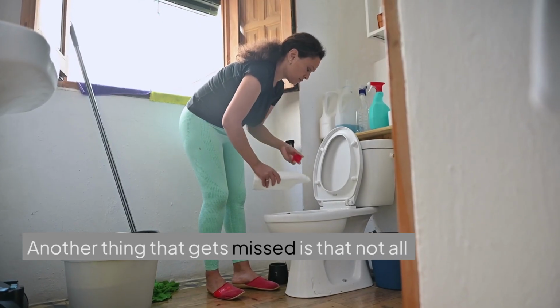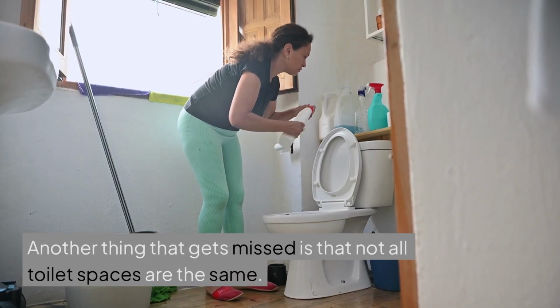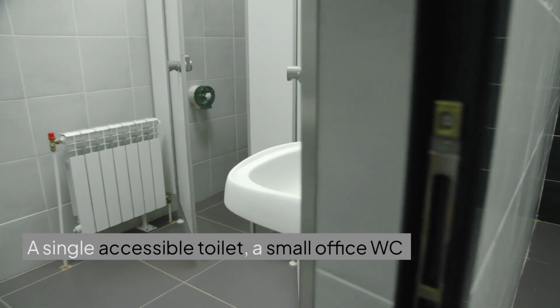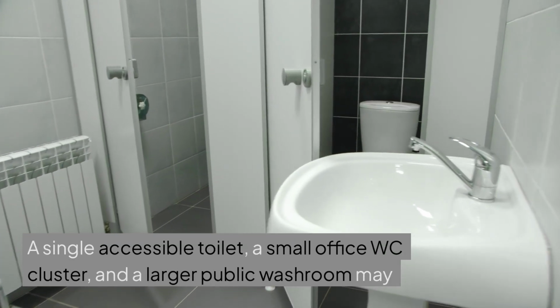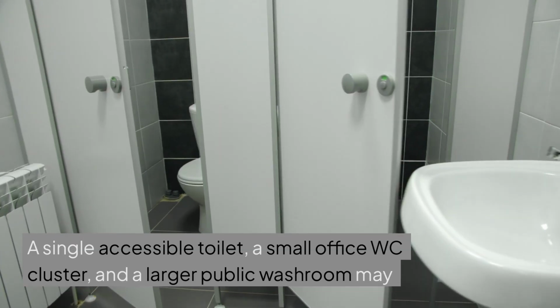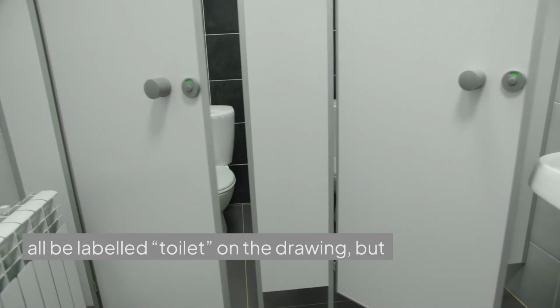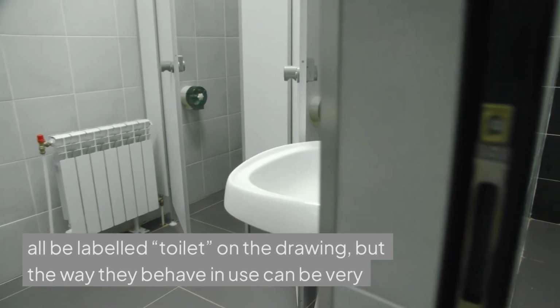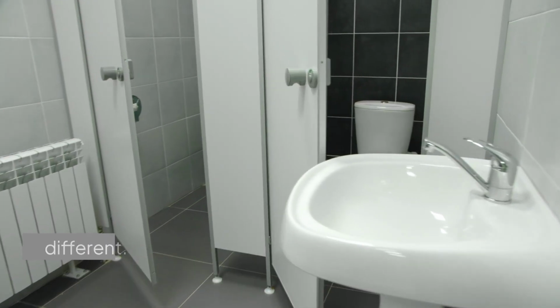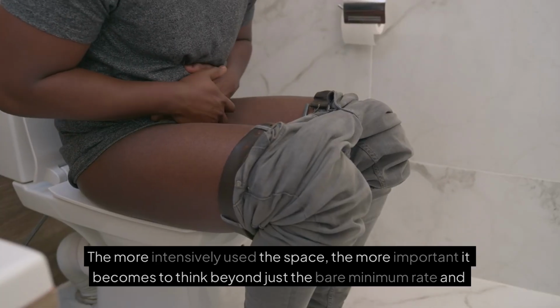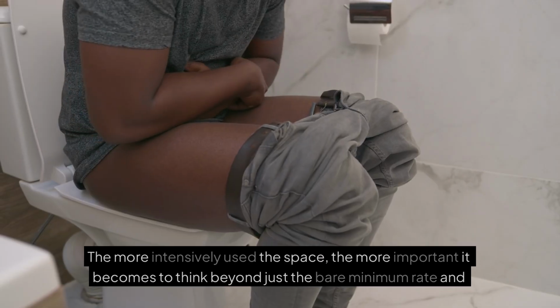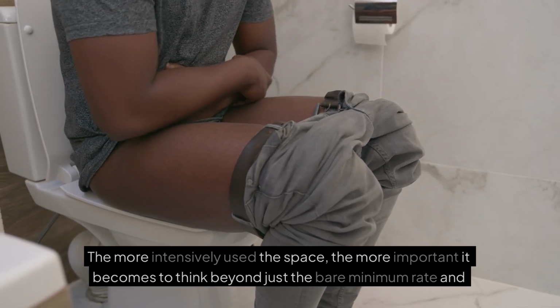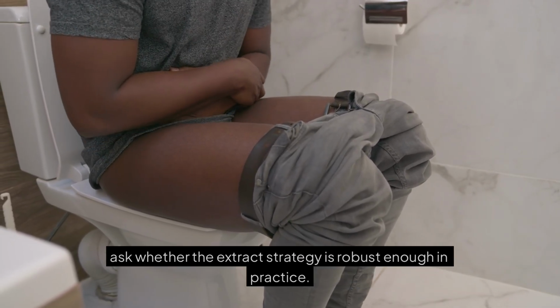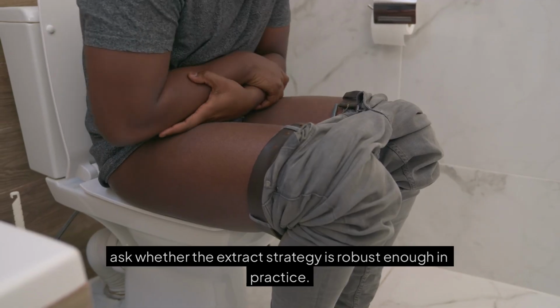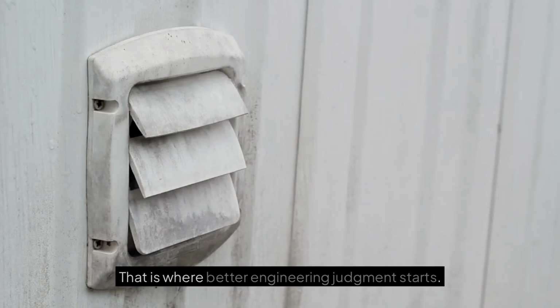Another thing that gets missed is that not all toilet spaces are the same. A single accessible toilet, a small office WC cluster, and a larger public washroom may all be labeled toilet on the drawing. But the way they behave in use can be very different. The more intensively used the space, the more important it becomes to think beyond just the bare minimum rate and ask whether the extract strategy is robust enough in practice. That is where better engineering judgment starts.